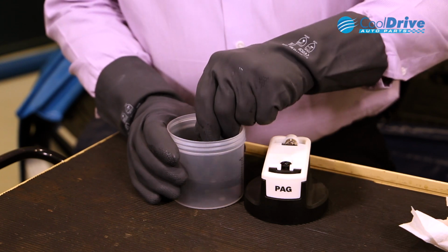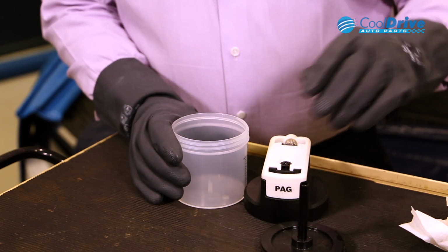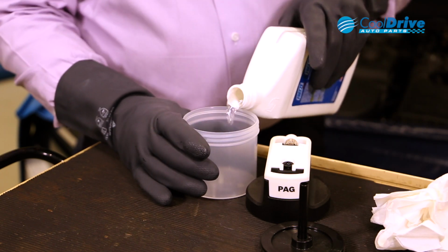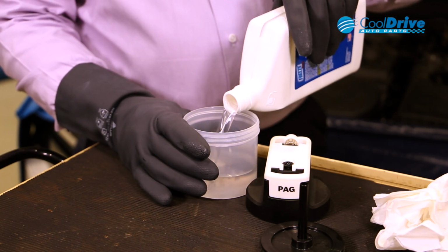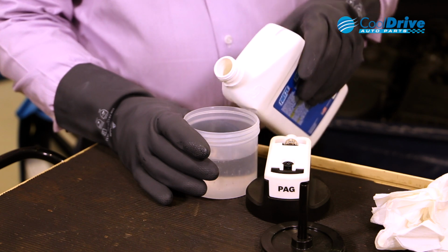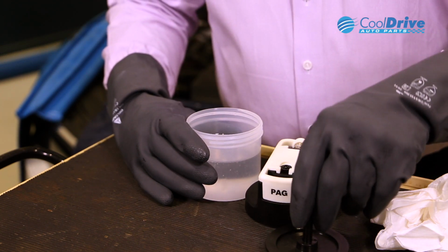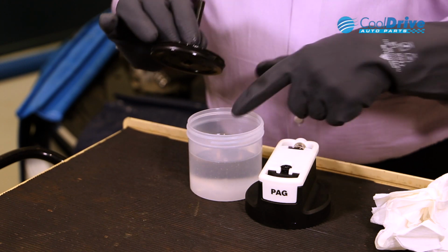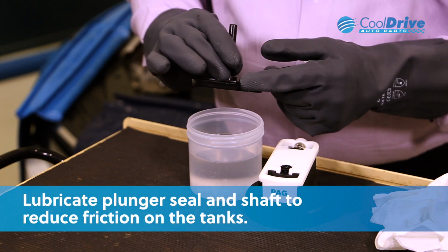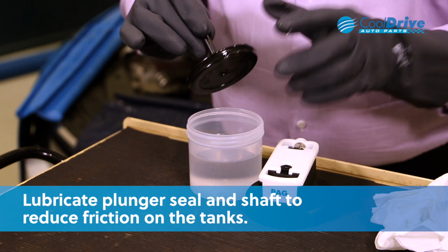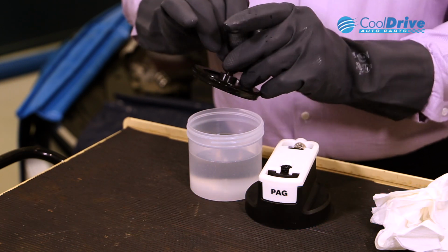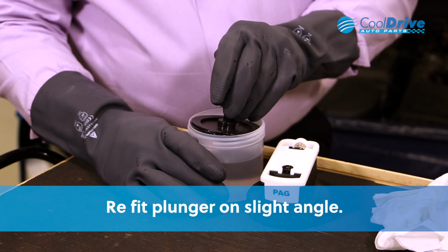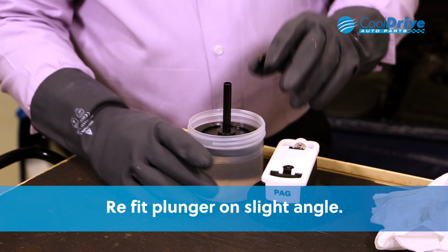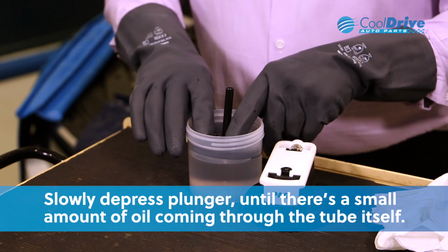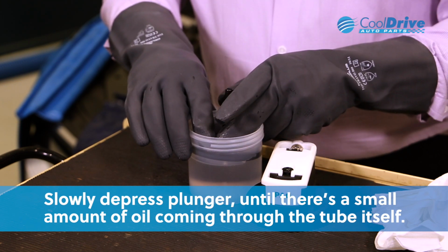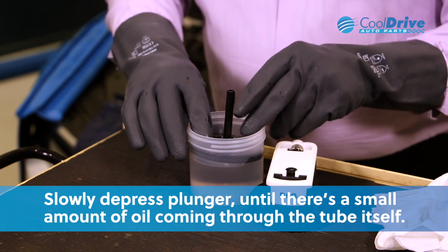You want to remove the plunger, fill the actual container, and before actually putting the plunger back in, it's wise to actually lubricate the seal around the plunger itself and the shaft. Refit the plunger back on a slight angle, and then slowly depress the plunger until there's a slight amount of oil coming through the tube itself.